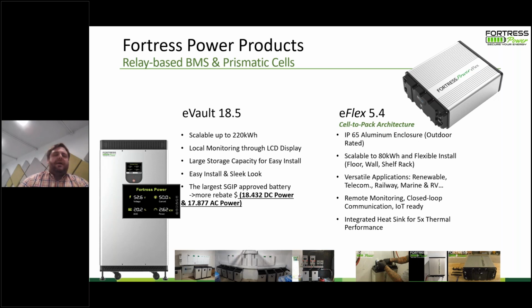If you just have one battery inverter and want one battery with one set of conductors between the battery inverter and the battery in a simple install, the eVault is the way to go. If you know what you're doing and have an easy to access job site, you can literally uncrate the eFlex, wheel it into place, run one set of conductors between the battery and the battery inverter, press the power button, program the inverter, and you're fully installed and commissioned. It's possible to install and commission an eVault project in one or two man hours.